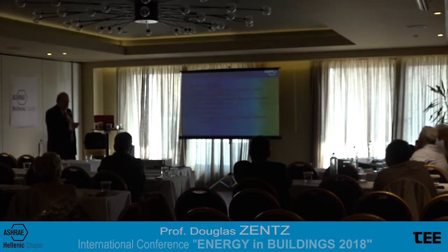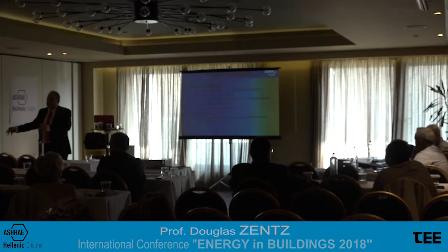If you're familiar with Appendix G in 90.1, that is, how do I create what's called a baseline model for my energy consumption of my type of building? There is a similar appendix, it's called a normative appendix in this standard, which sets up the same reference. You can model what a standard building would be and then look at the performance of your building against that standard.